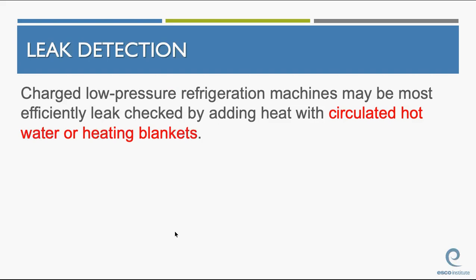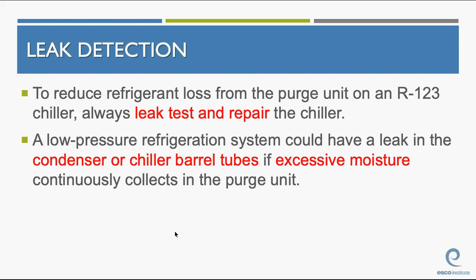Charged low pressure refrigeration systems may be most effectively leak checked by adding heat with circulated hot water or heating blankets. To reduce refrigerant loss from the purge unit on an R123 system chiller, always leak test and repair the chiller. A low-pressure refrigeration system could have a leak in the condenser or chiller barrel tubes if you find excessive moisture in the purge unit.